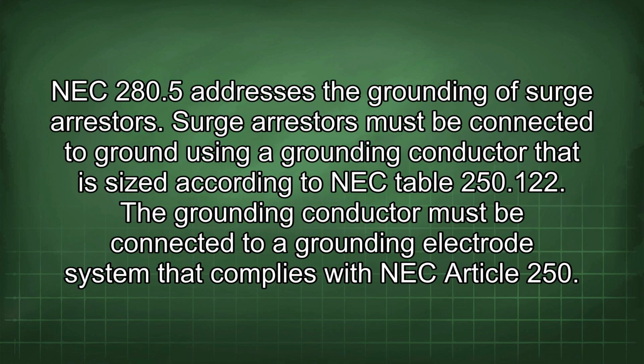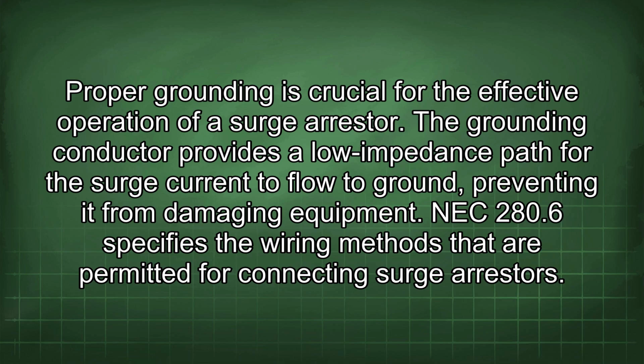NEC 280.5 addresses the grounding of surge arrestors. Surge arrestors must be connected to ground using a grounding conductor that is sized according to NEC Table 250.122. The grounding conductor must be connected to a grounding electrode system that complies with NEC Article 250. Proper grounding is crucial for the effective operation of a surge arrestor. The grounding conductor provides a low impedance path for the surge current to flow to ground, preventing it from damaging equipment.